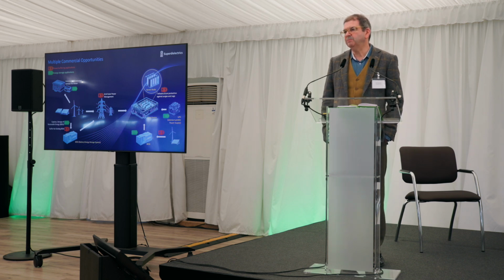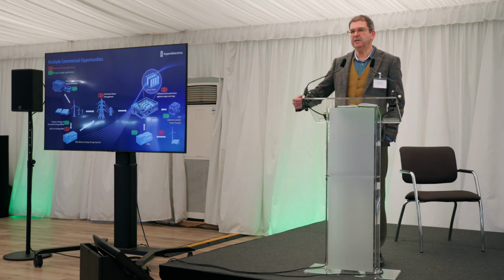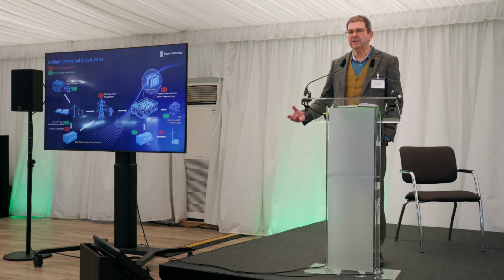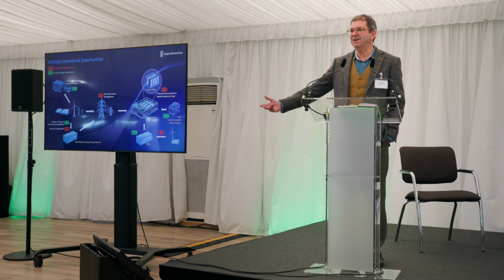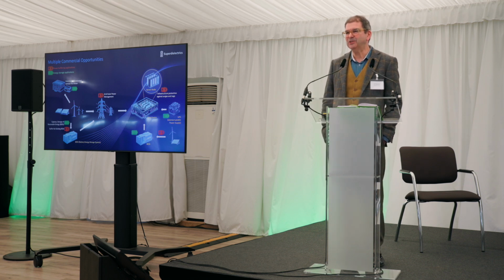That means the power demand to the server will plummet from several hundred megawatts down to, well, it can drop by as much as 80 or 90% in milliseconds. And of course, before that drop happens, the grid, the local substation, the infrastructure at the data center is running with high power coming through it, and that power has to go somewhere.